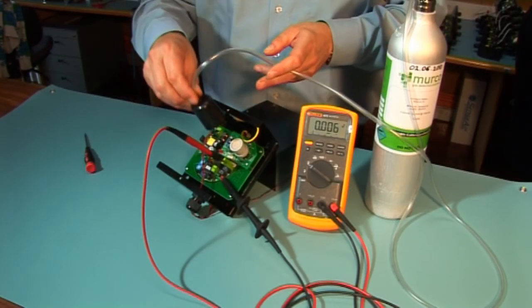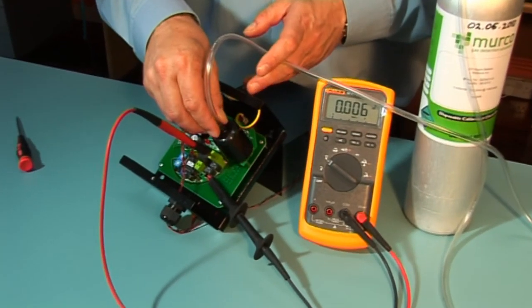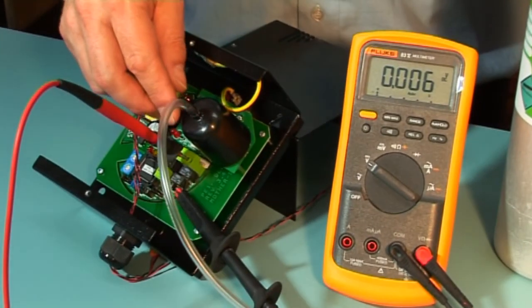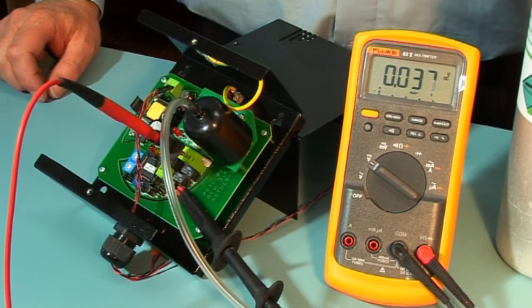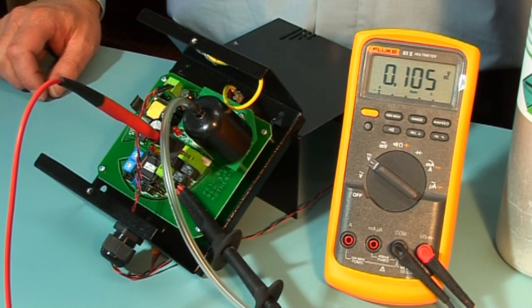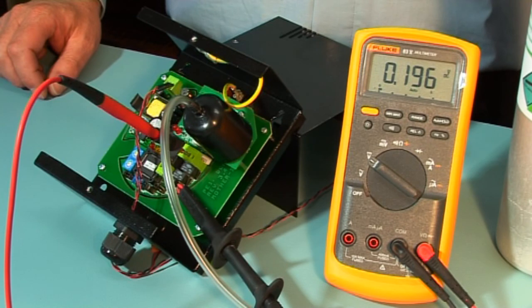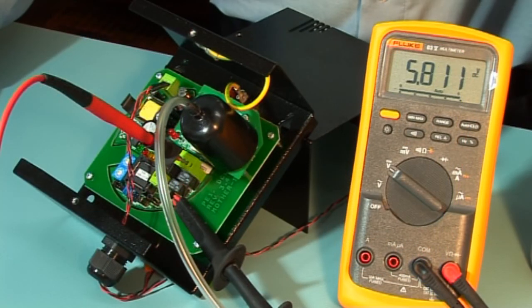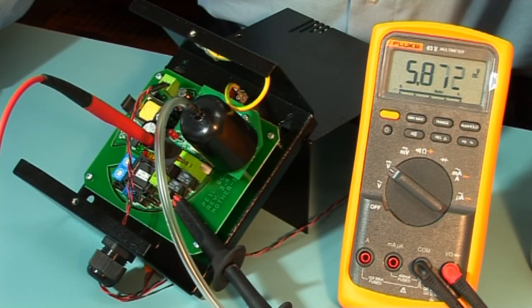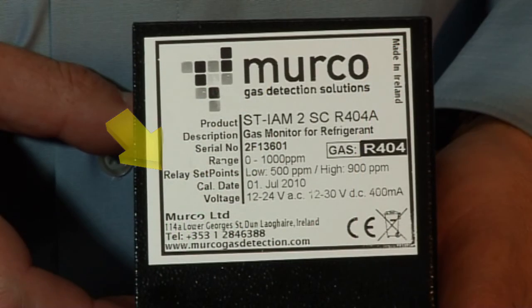Expose the sensor by introducing gas to the sensor here, and you should see the voltage increase. It may take 10 to 15 minutes to reach full scale on the sensor output. Older sensors may take longer. Observe the voltmeter output when the unit goes into alarm. This should correspond to the alarm set point on the rating label, which should be the factory setting or a previous local change.